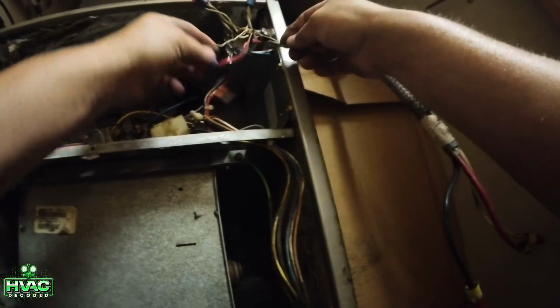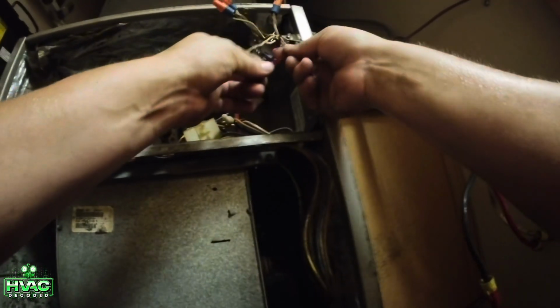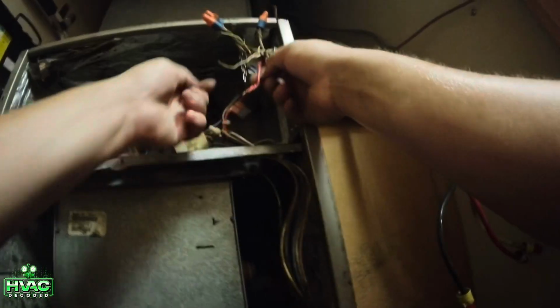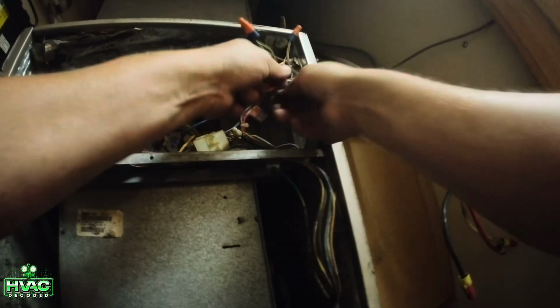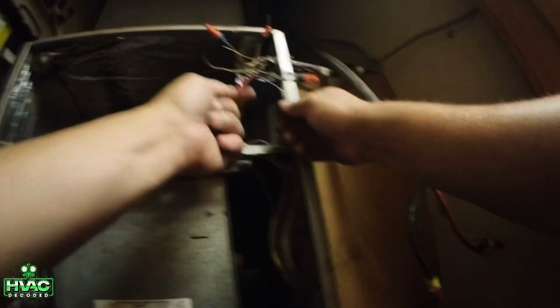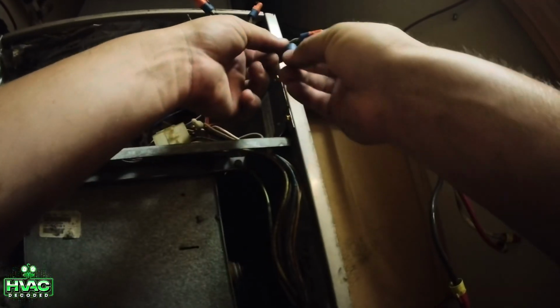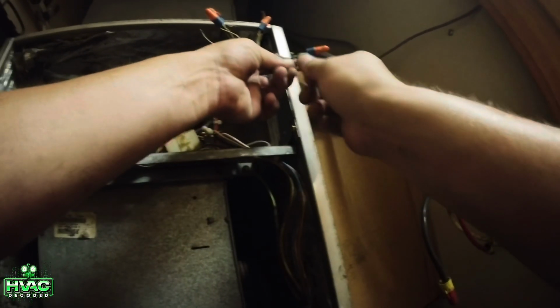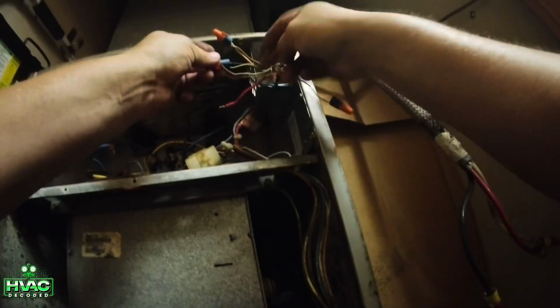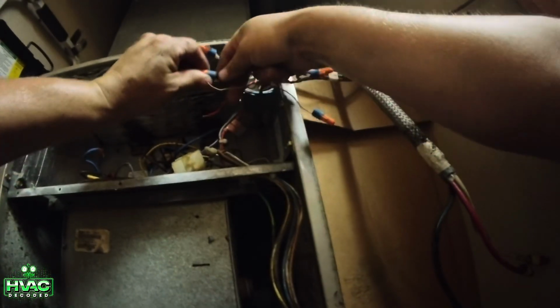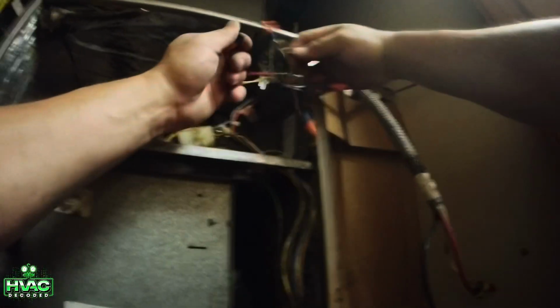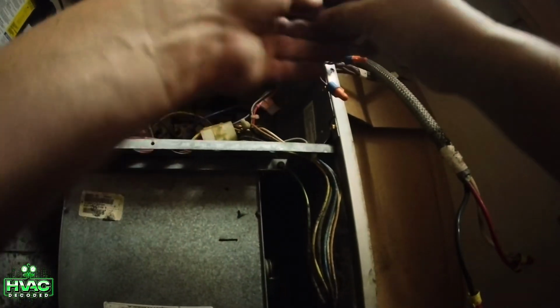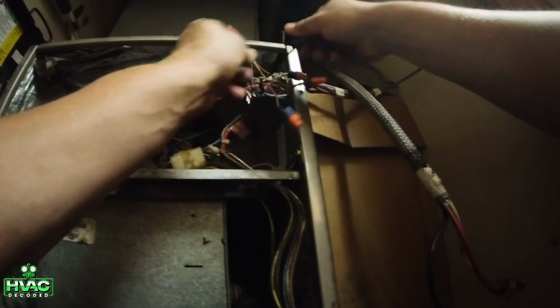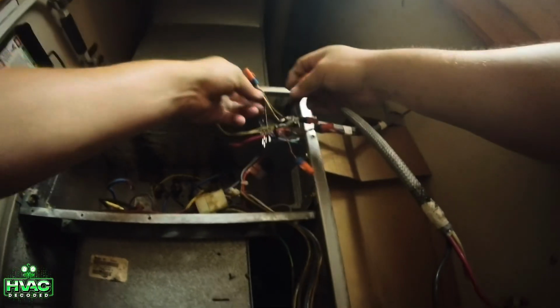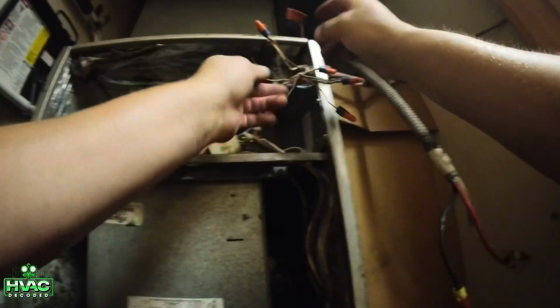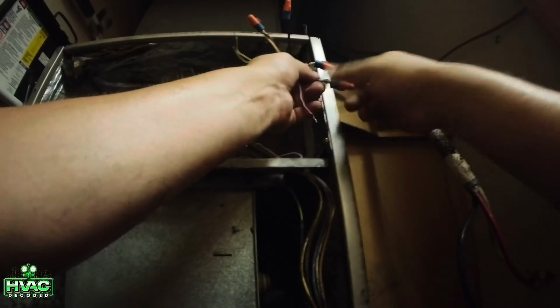So, from your thermostat, you've got your red, your main power, okay, goes to your red here on the system unit, air handler. And you've got your cooling, which is yellow on the thermostat, connected to the condenser, which on this one is black for the condenser. Black and white, as you can see, these two. Your condenser outside, I'm sorry, yellow's cooling, okay, and green is your fan.